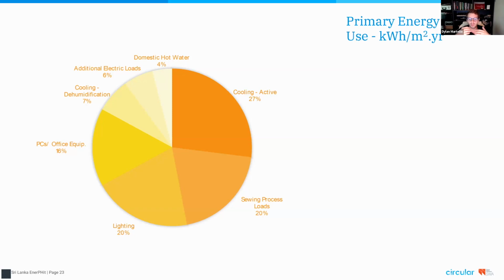While you can get a wattage or power draw from a piece of equipment like a sewing machine, that doesn't tell you how often it's used and how often it's running at that power draw. So we really had to hone in on how often that motor is running. Over about a minute and a half sample size that we took, and we did this multiple times, the motor was running for about 15 seconds, or roughly 15% of the actual time we sampled. That helped us define our assumptions for how often this equipment was running at that power load.